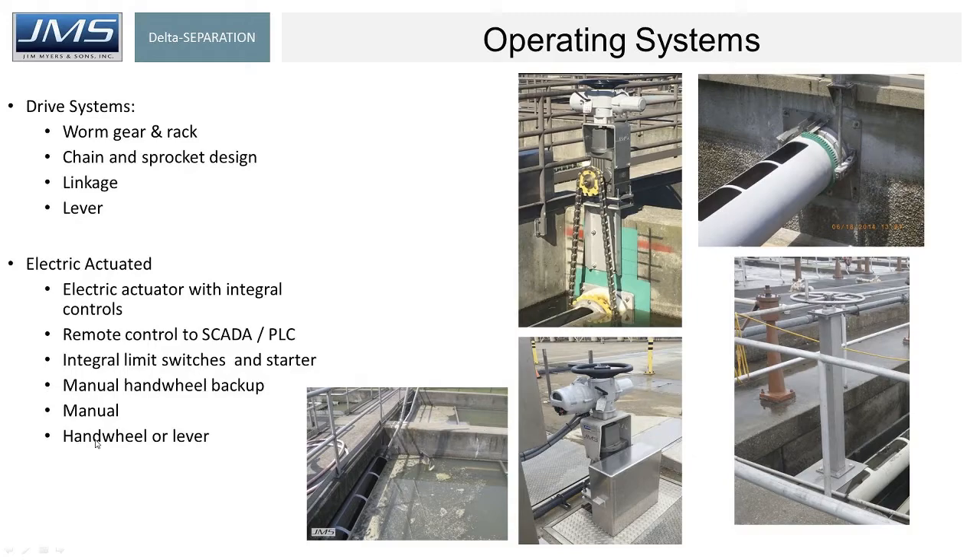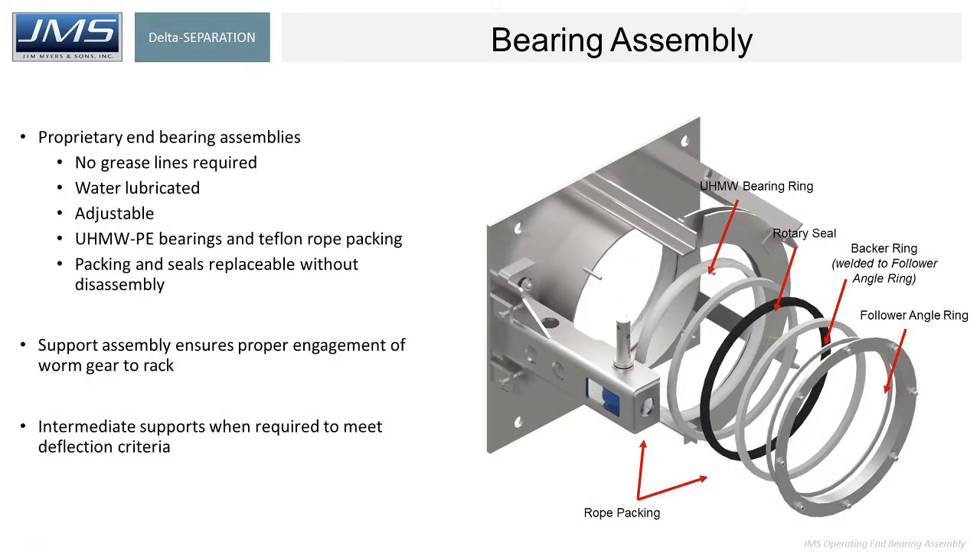Of course, an electric actuator has a manual handwheel backup as well so that you have a fallback. The key design considerations for the end bearing assemblies are that they need to be adjustable — that's key, because over time the worm gear engaging with the rack on the pipe, when that's the operating system, it's important for it to be adjustable in all directions: X, Y, and Z axes. It's also important for the seals to be able to be adjusted with a follower angle ring to tighten the seals over time. Those are the key design considerations when evaluating a scum pipe system.